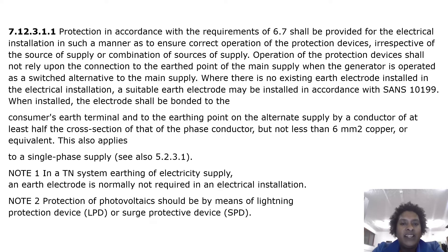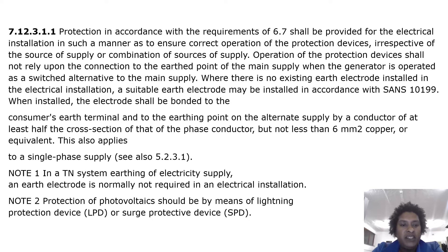When installed, the electrodes shall be bonded to the consumer's earth terminal and to the earthing point on the alternative supply by a conductor of at least half the cross-section of the phase conductor, but not less than 6 mm² copper or equivalent. This also applies to a single phase supply. Note 1: in a TN system, an earth electrode is normally not required in an electrical installation. Note 2: protection of photovoltaics should be by means of a lightning protection device or surge protective device.